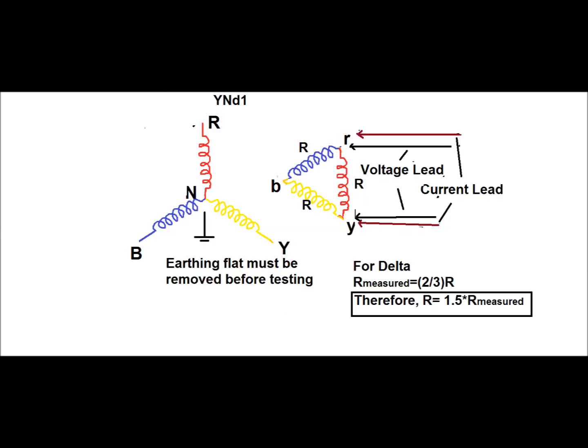How the resistance of the delta winding can be measured is shown in this diagram. For a delta winding, if the resistance of each phase winding is R, the measured R should be equal to 2/3 of R. Therefore, the actual R can be calculated: actual R is equal to 1.5 times the measured R.